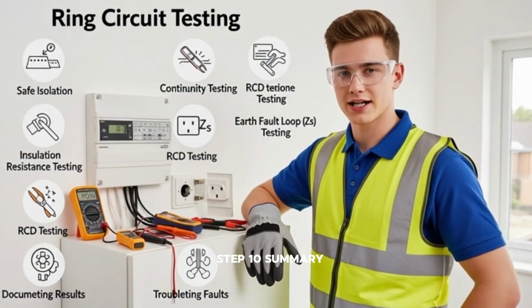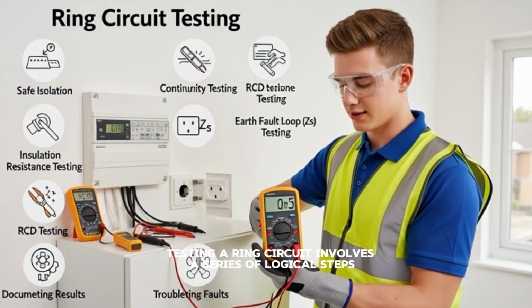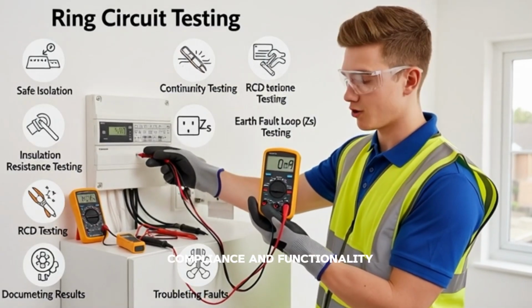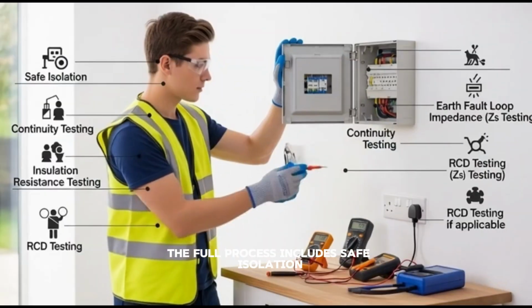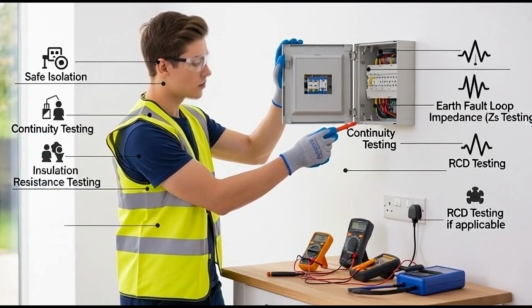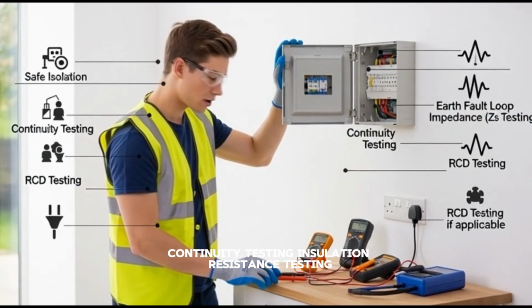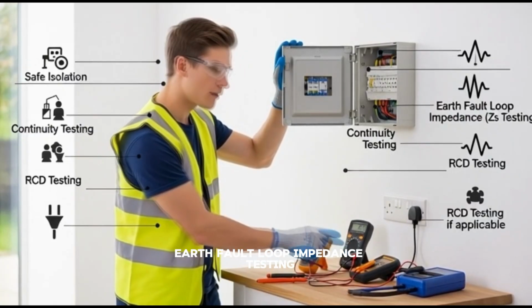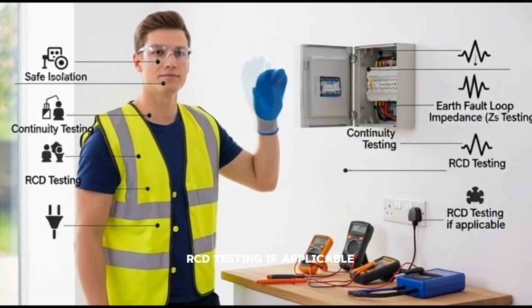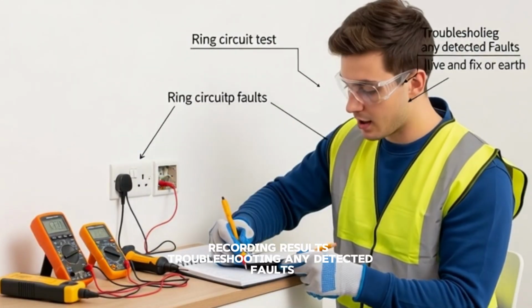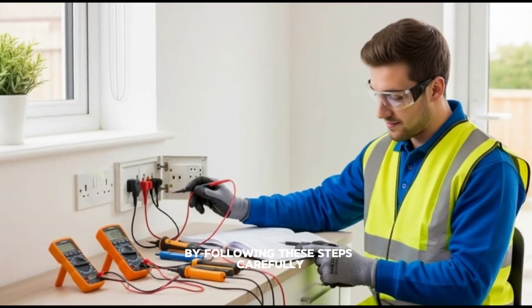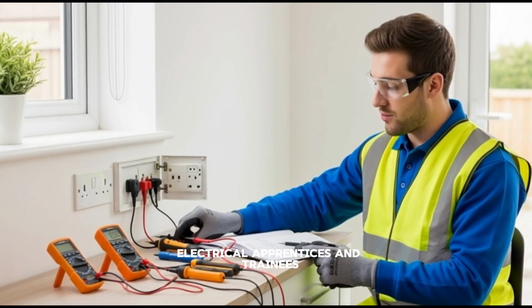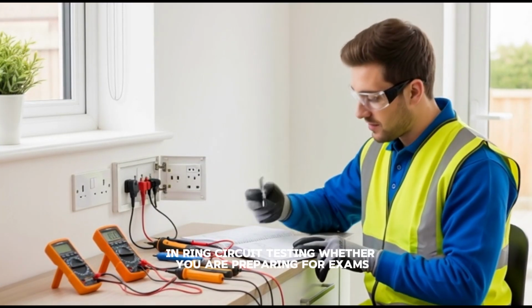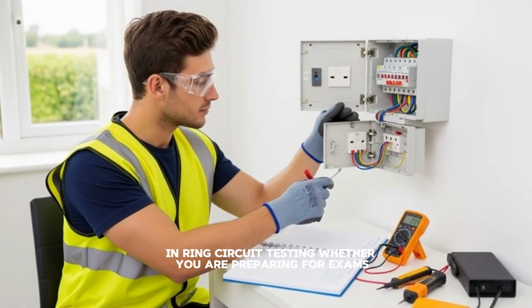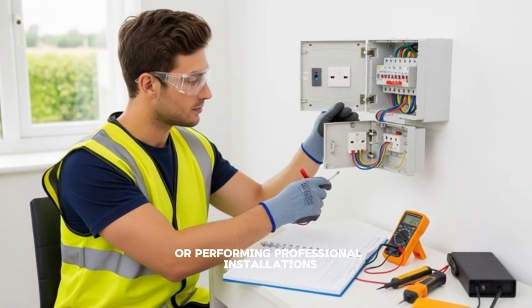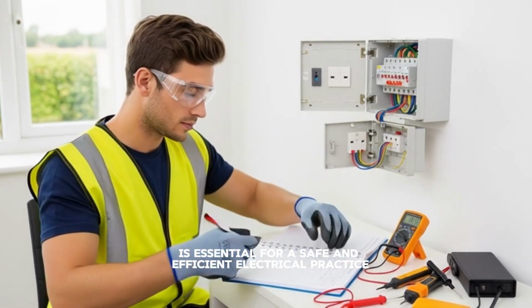Step 10. Summary. Testing a ring circuit involves a series of logical steps designed to ensure safety, compliance, and functionality. The full process includes safe isolation, continuity testing, insulation resistance testing, earth fault loop impedance testing, RCD testing if applicable, recording results, and troubleshooting any detected faults. By following these steps carefully, electrical apprentices and trainees can build confidence and competence in ring circuit testing.